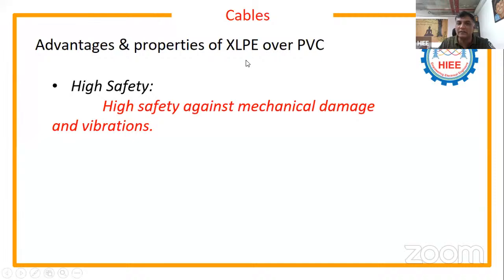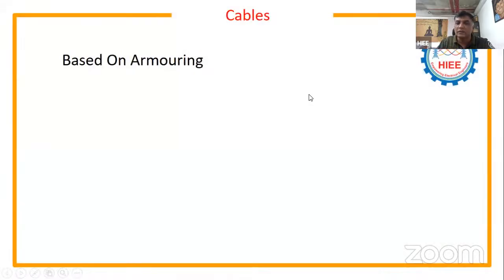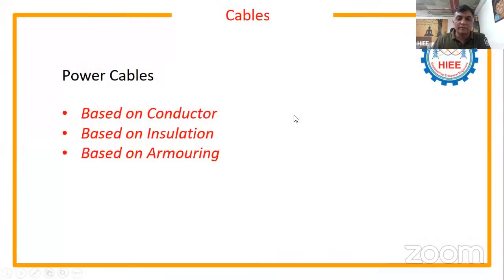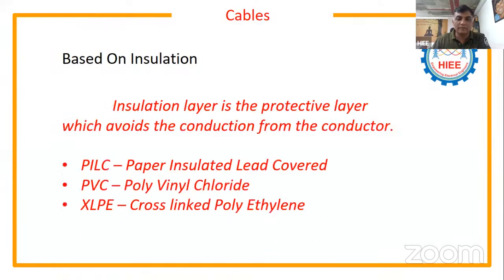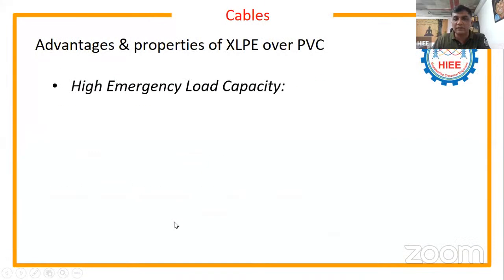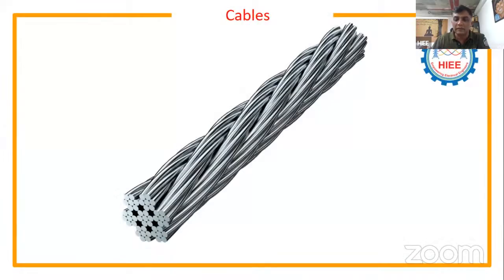And of course, safety, because XLPE mechanical strength is higher than PVC insulation. So obviously there is higher safety against mechanical damage and vibrations when you're going with XLPE compared to PVC. Okay, so that is about insulation around the conductor. We use PVC, XLPE and paper insulated material, isn't it? Three insulations we use: paper insulated lead covered, polyvinyl chloride, and XLPE, crosslinked polyethylene. These are the three insulations we use above the conductor.